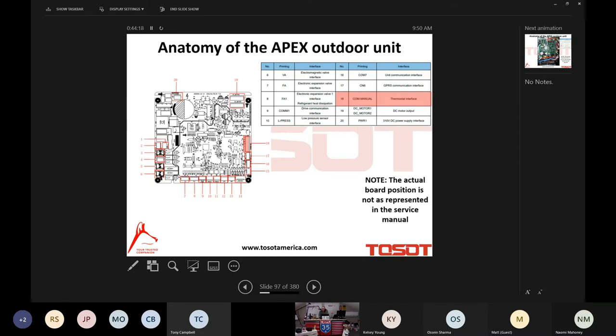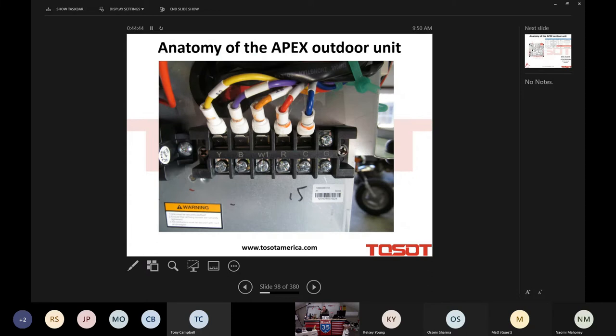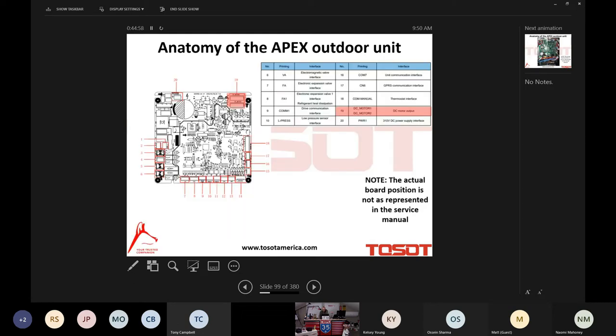Okay, the thermostat interface. I actually don't like that description. This is really, I think, better described as the communication interface, because we're not hooking up our thermostat to the outdoor unit. You know that. We're hooking it up to the indoor unit. But there is communication, 24-volt communication, from the outdoor unit to the indoor unit and vice versa. And that's what this is. This is our communication circuit, YBW1, R, C, and G, the same nomenclature that we saw for our thermostat connections of the indoor unit. But this is our communication between the outdoor and the indoor unit.